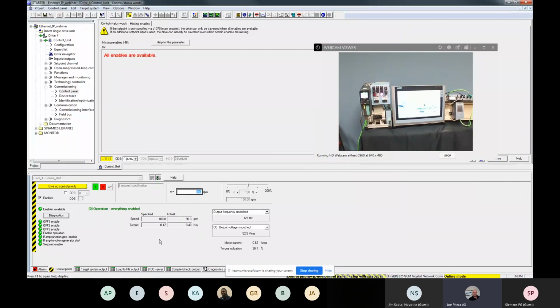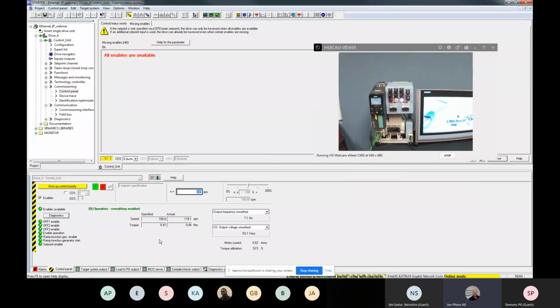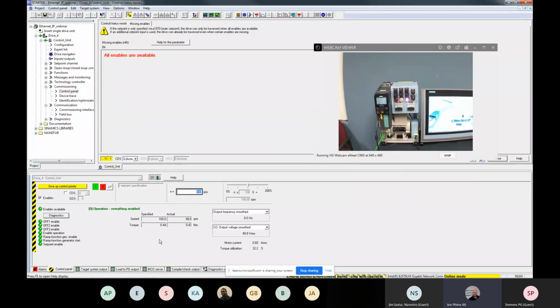You actually see that it is operating here. I do have a little bit of a brake action on it. And I don't know if you can see that, but I put a rubber band on a leather brake that's around the output of the shaft there, so it is causing a pulsating type of load on this. I don't know if you can see that, if it's updating fast enough on the screens. Probably not, due to video refresh rates. But we can actually monitor the load there as well.